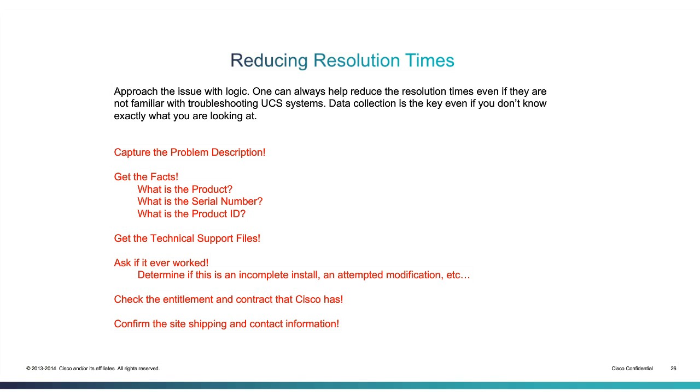If you find out that it was just a new installation, experience might lead you to go to the firmware installation to make sure you're not dealing with a board activation failure or a CIMC activation failure or something like that, or maybe even on the adapter if you notice that there is a difference between the starting version and the running version.